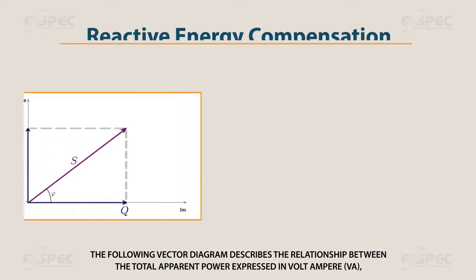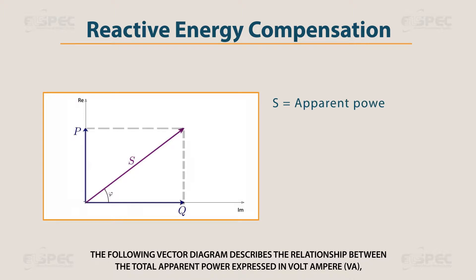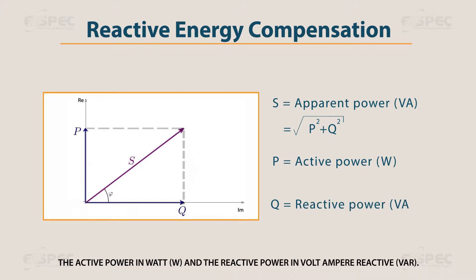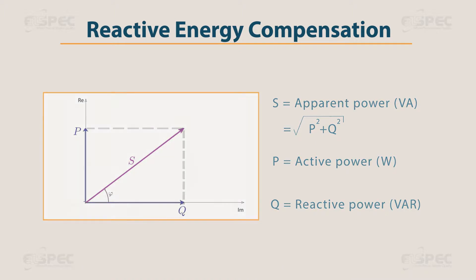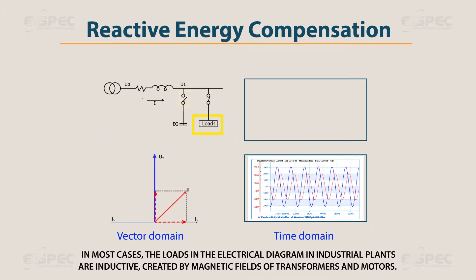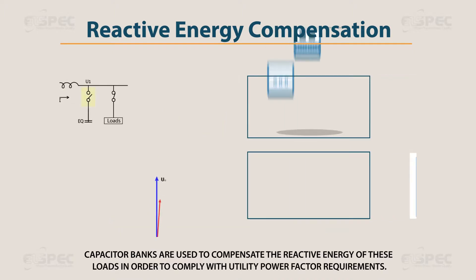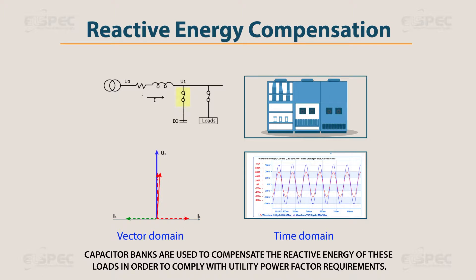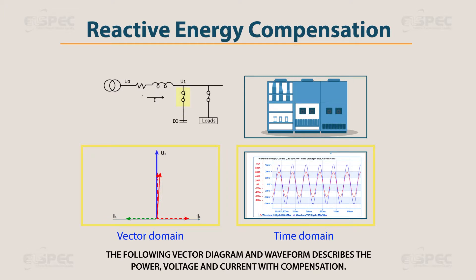The following vector diagram describes the relationship between the total apparent power expressed in volt-ampere, the active power in watt, and the reactive power in volt-ampere reactive. The graph shows the current and voltage in time domain and in vector domain. In most cases, the loads in the electrical diagram in industrial plants are inductive, created by magnetic fields of transformers and motors. Capacitor banks are used to compensate the reactive energy of these loads in order to comply with utilities' power factor requirements. The following vector diagram and waveform describes the power, voltage, and current with compensation.